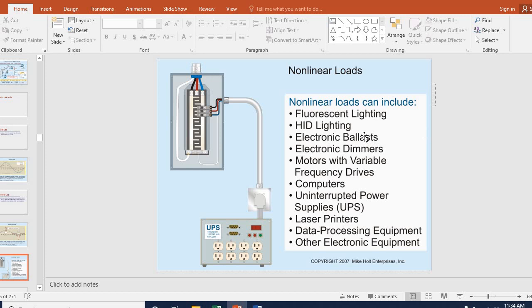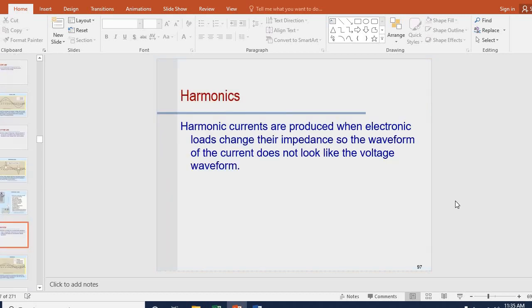Now you get into some nonlinear loads. Can include fluorescent lighting, HID lighting, electronic ballast, dimmers, motors, frequency drives, computers, UPSs, printers, other equipment. Might not pull the same thing.